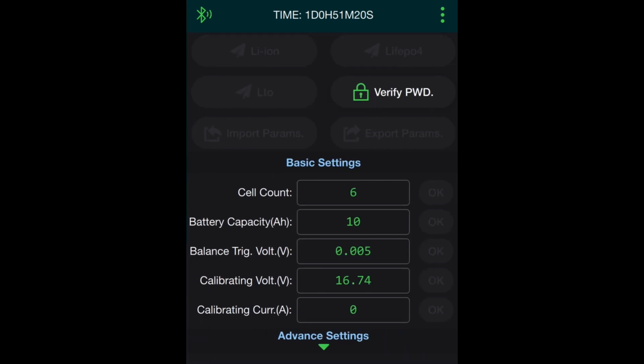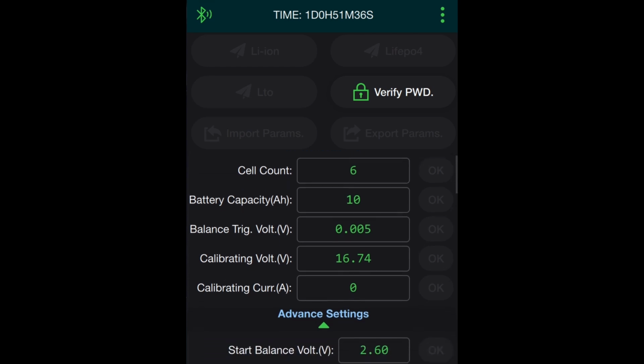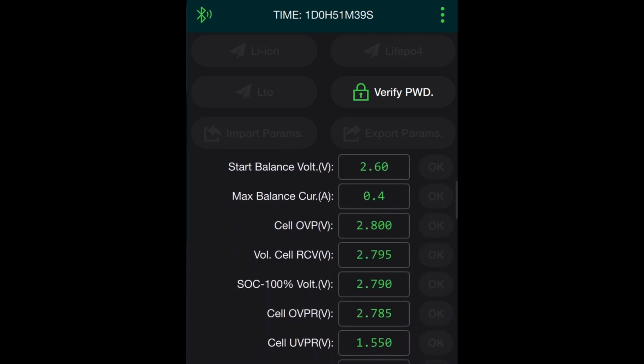Now, let's look at the battery management system settings. We have 6 cells, and the balancer is set to 5 millivolts. The cell balancing starts at 2.6 volts, and the maximum balance current is 0.4 amperes. The cell overvoltage protection is set to 2.8 volts. The required charging voltage is set at 2.795 volts. A 100% charge is reached at 2.79 volts per cell. The cell overvoltage protection reset is at 2.785 volts.